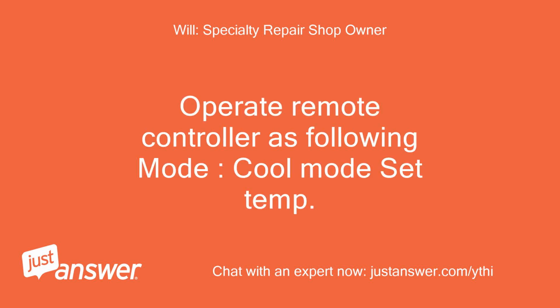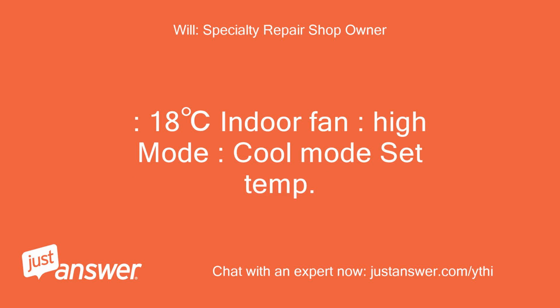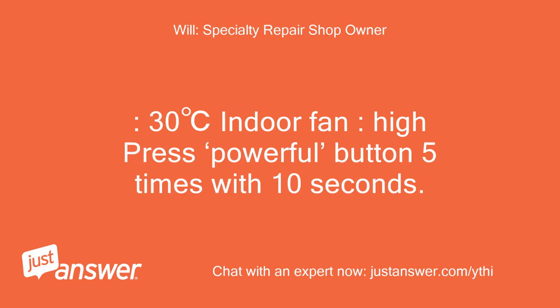Operate the remote controller in the following modes. Cool mode, set temp 18C, indoor fan high. Cool mode, set temp 16C, indoor fan high. Heat mode, set temp 28C, indoor fan high. Heat mode, set temp 30C, indoor fan high. Press the powerful button 5 times within 10 seconds.